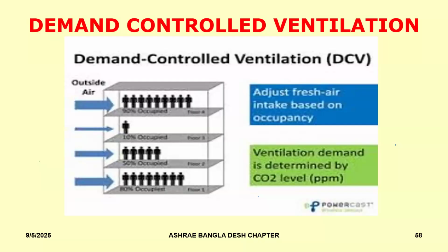So we need to then measure what is the CO2 level, what is the VOC level, etc., and then decide how much of outside air will be pumped into that space. But in most cases, the ventilation demand is based on occupancy, which means based on CO2 level. But like I said, if your indoor pollutant like a VOC concentration is also going up, then you could also modulate that outside air based on VOC demand. So how do you modulate this?